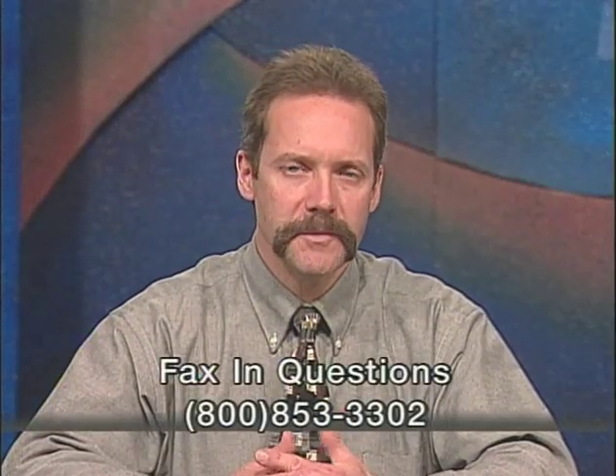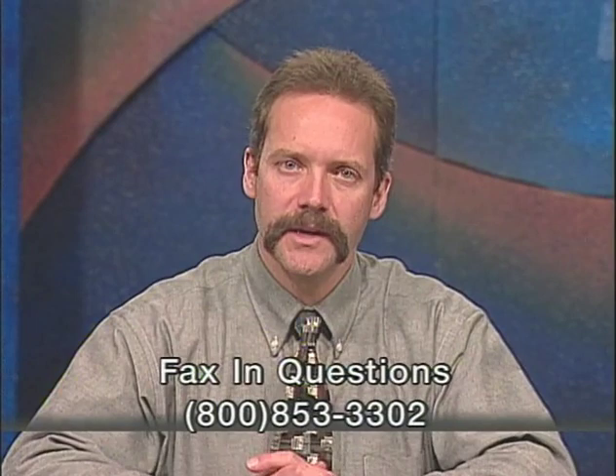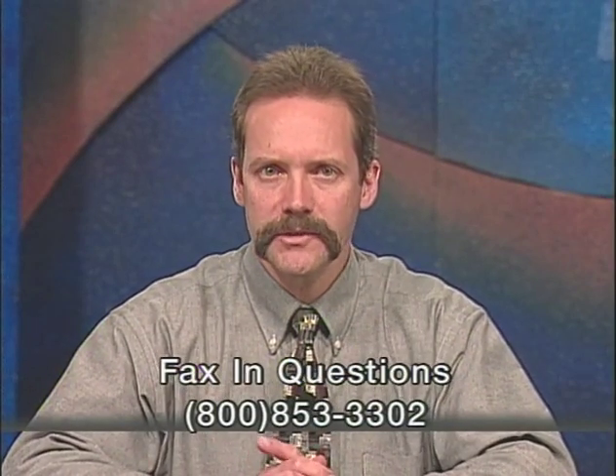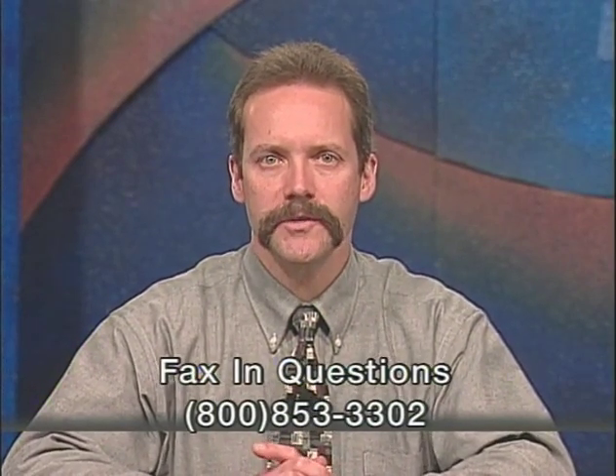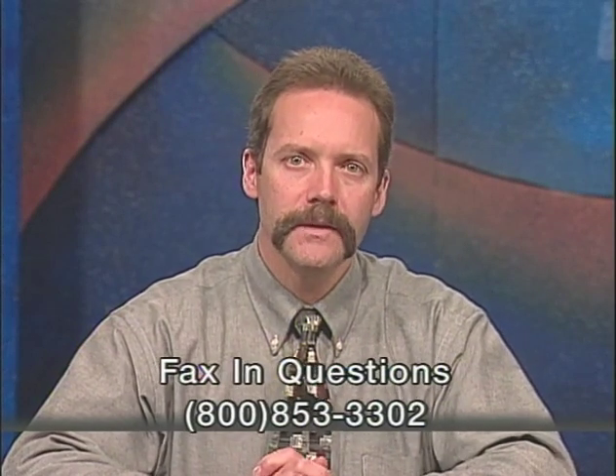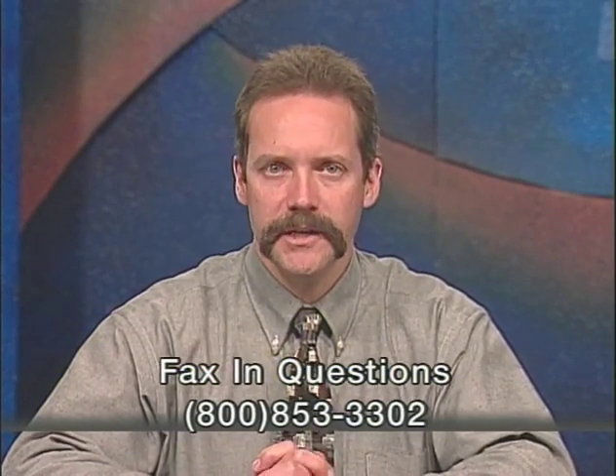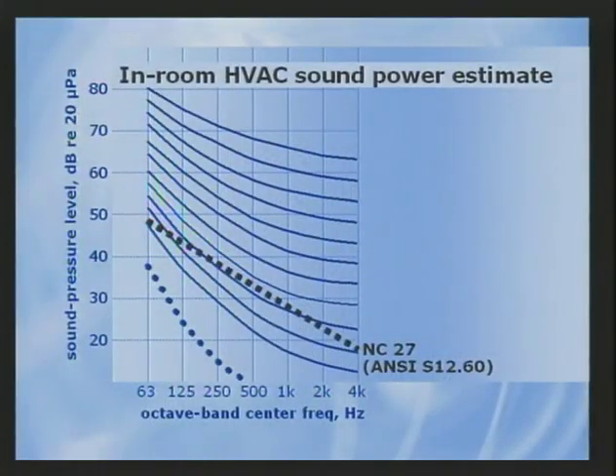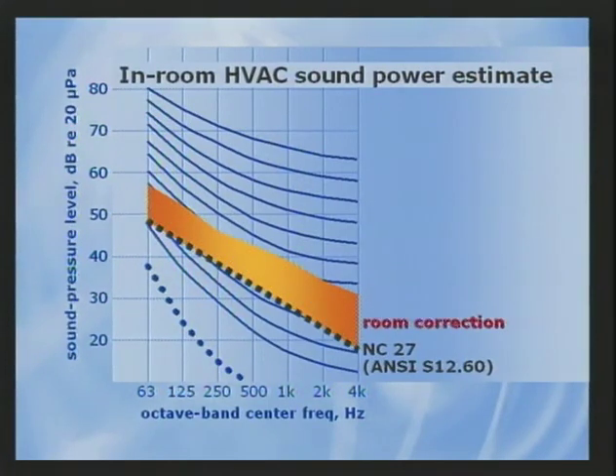But before we do that, let me make it clear that we're looking at one example case. Do not translate the results of this one example or any of the other cases I'll review to make a general statement. Each situation is unique and should be individually modeled. Okay. Using an RC curve to generate octave band sound levels from the 35 dBA requirement, we can back into the required sound level for the in-room unit. This figure shows the room correction added to the 35 dBA spectrum. The top line is the octave band sound power requirement for the in-room unit.